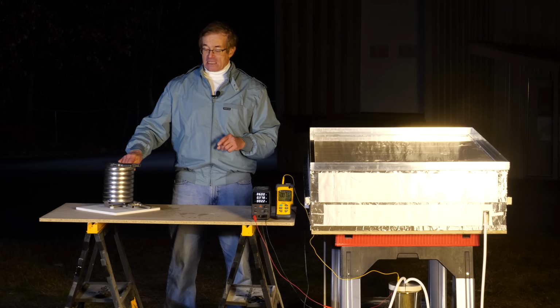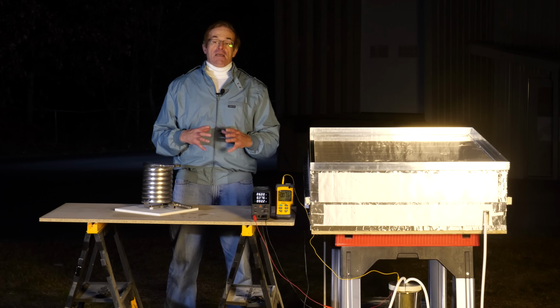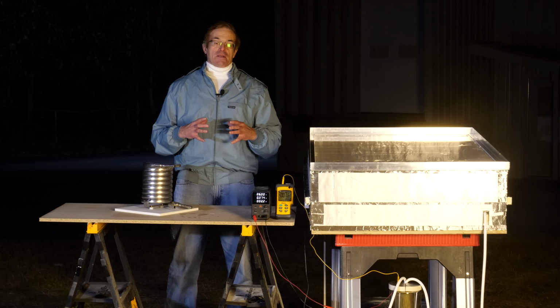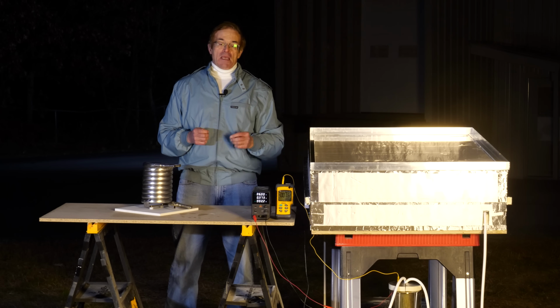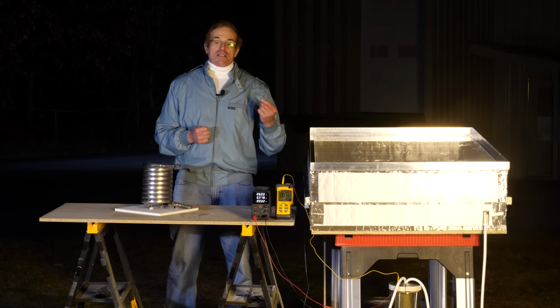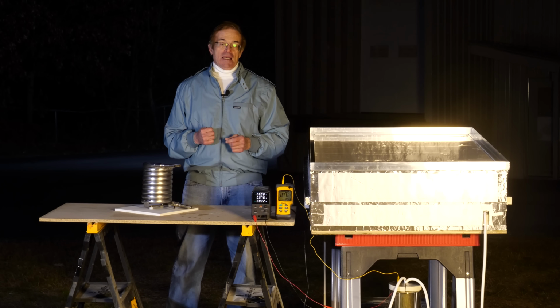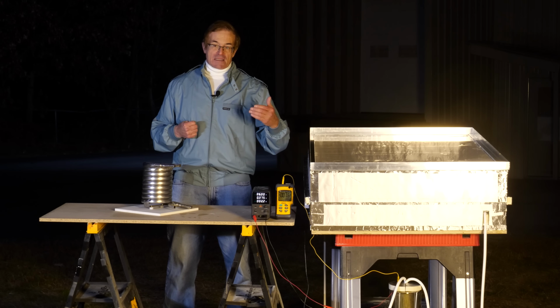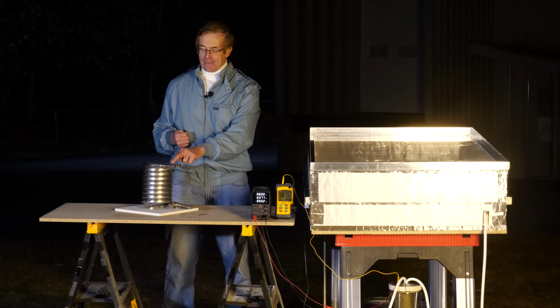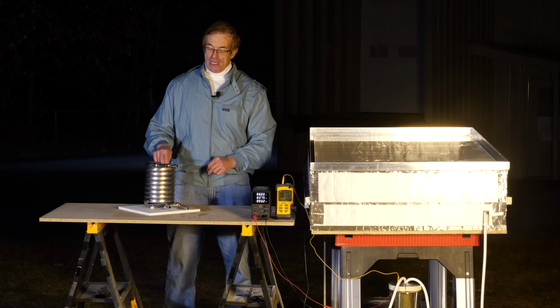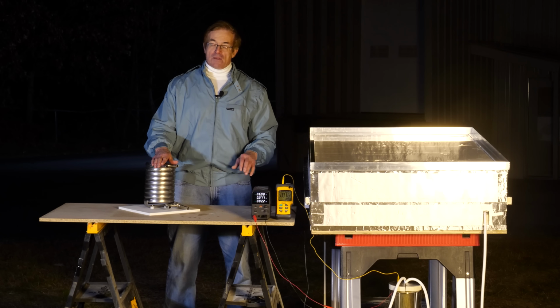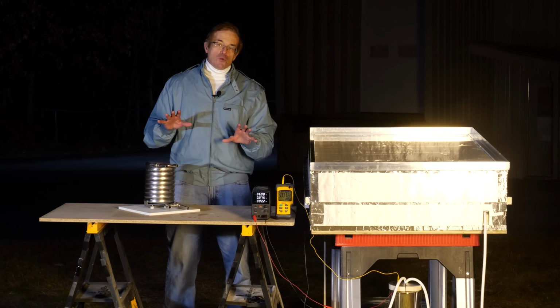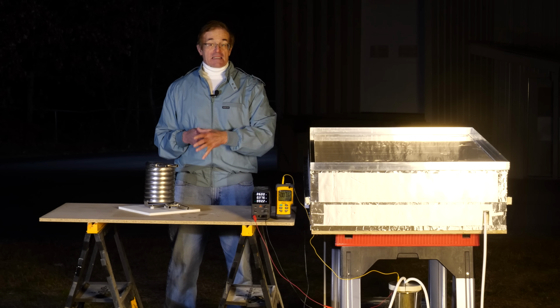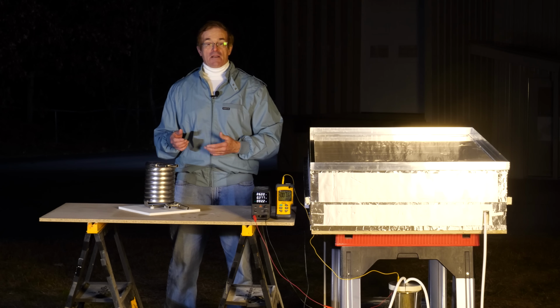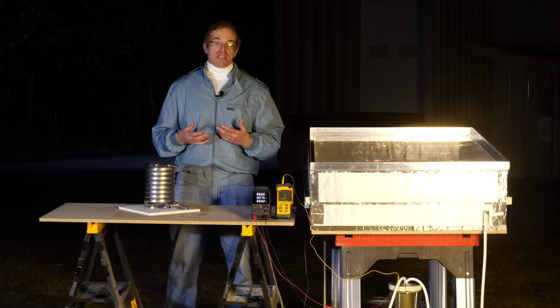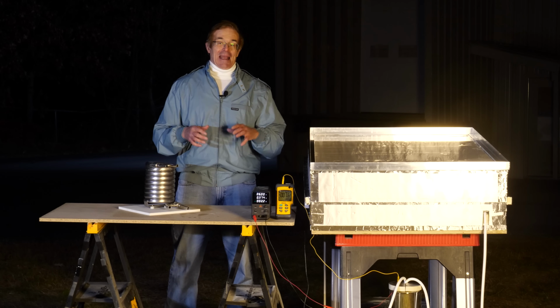Another method might be if you have a split cycle air conditioner or a heat pump where the compressor outside compresses the refrigerant and then dumps the majority of the hot refrigerant heat into the radiator using the large fan outside the structure. You remember that you can't get that fluid temperature even as low as the outside air temperature. It can never equal the air temperature. So what you could do is flow that liquid that's come out of your radiator after it's dumped the majority of its heat through a liquid-to-liquid heat exchanger, where you circulate some of the fluid from the chiller around the refrigerant after it's dumped most of its heat, fooling your air conditioner system into thinking it's a little bit cooler outside, boosting its efficiency, and you still retain all the benefits of the heat pump or the air conditioner in dehumidifying or producing additional cooling during times when this system may not be operating at full capacity.